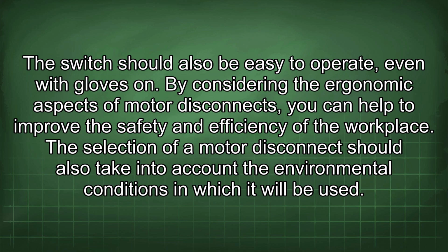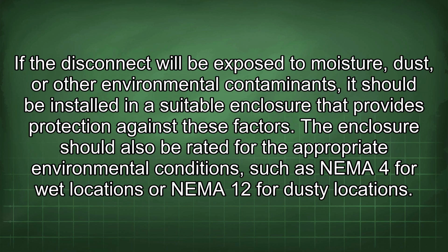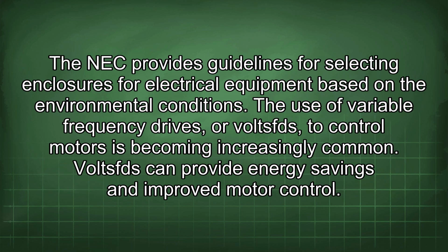The selection of a motor disconnect should also take into account the environmental conditions in which it will be used. If the disconnect will be exposed to moisture, dust, or other environmental contaminants, it should be installed in a suitable enclosure that provides protection against these factors. The enclosure should also be rated for the appropriate environmental conditions, such as NEMA 4 for wet locations or NEMA 12 for dusty locations. The NEC provides guidelines for selecting enclosures for electrical equipment based on the environmental conditions.